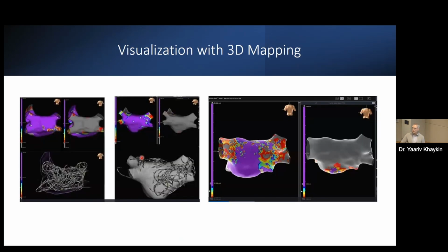Now, we're able to follow the catheter with 3D electroanatomical mapping systems. Again, we've been playing around with essentially virtual reality type technology since 1998, give or take. These are fairly sophisticated. They use magnetic guidance and impedance guidance to allow us to create 3-dimensional, very colorful maps of the heart that can represent electrical activity, normal voltage, abnormal voltage, the activation pattern around the heart, and we can also have the positions of the catheter on the heart in real time.